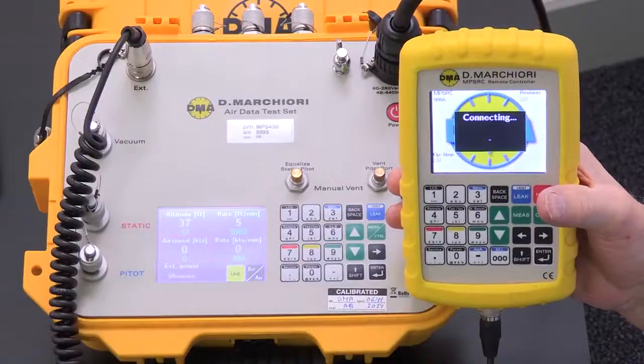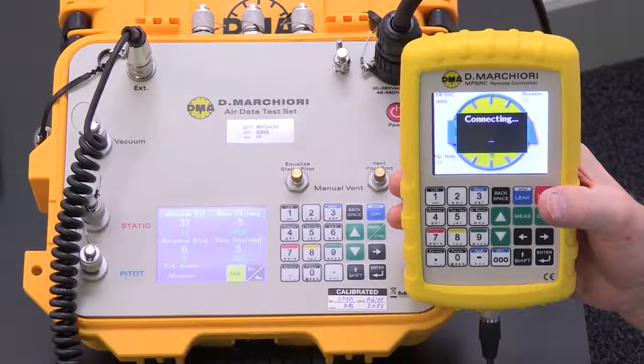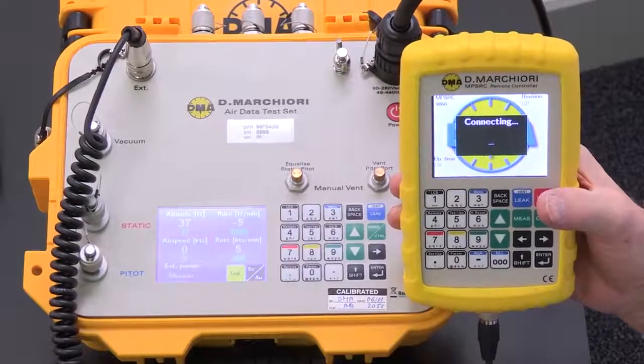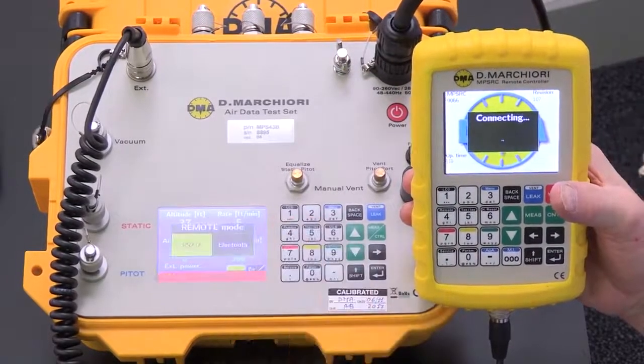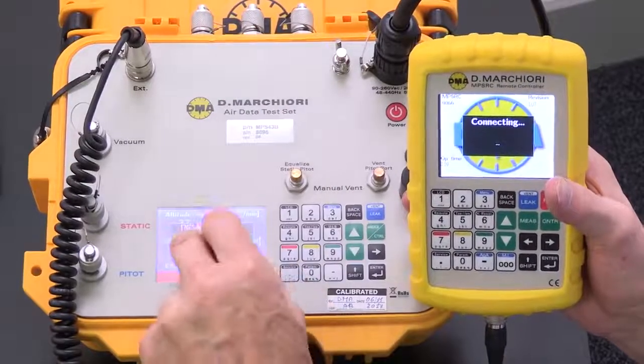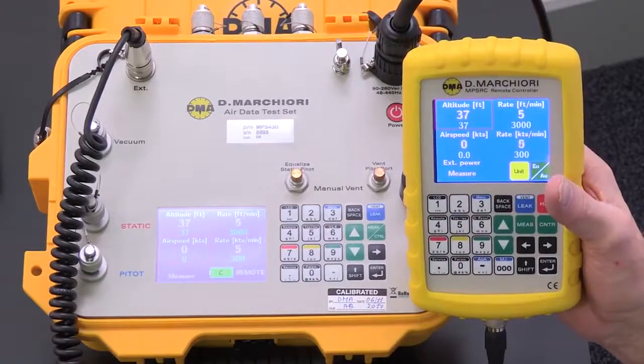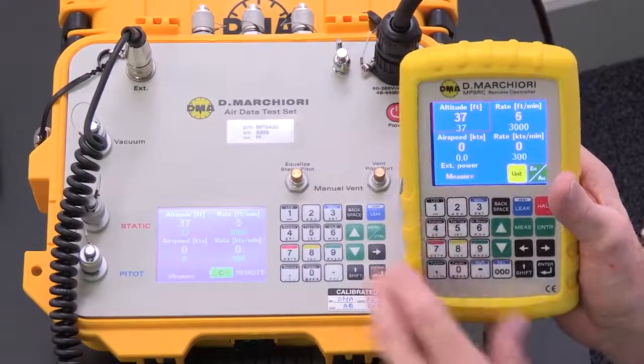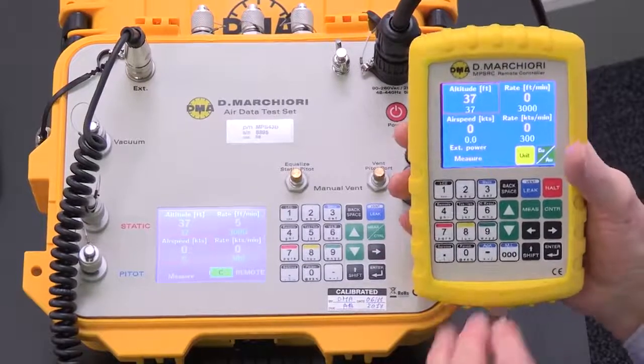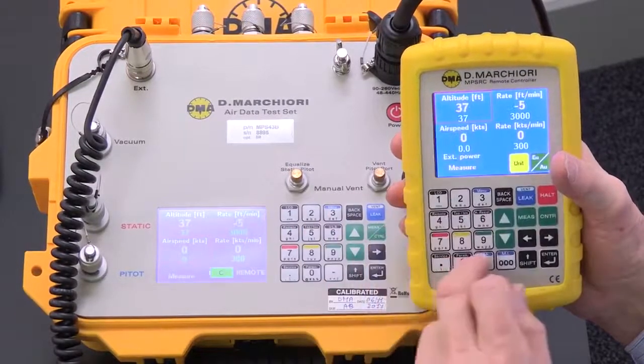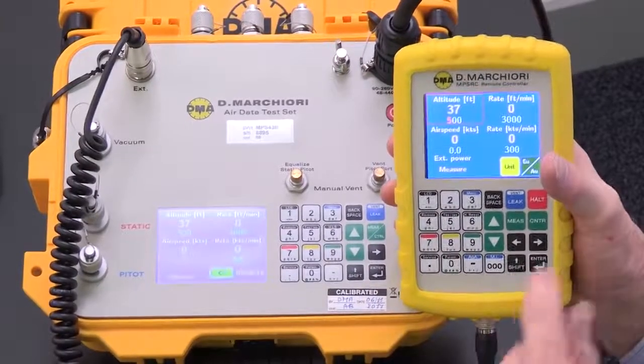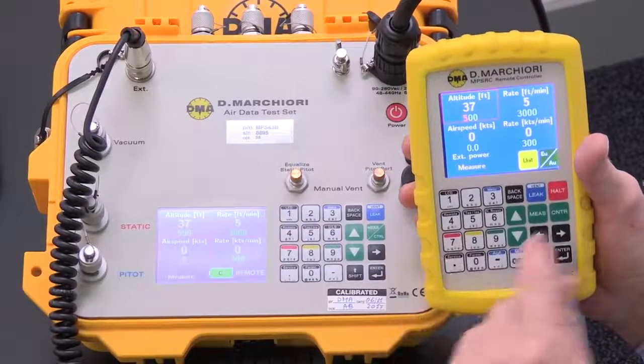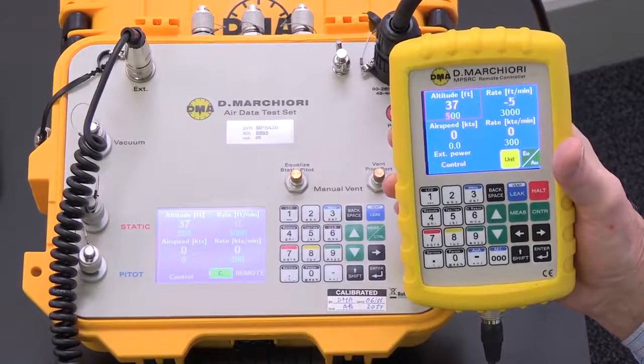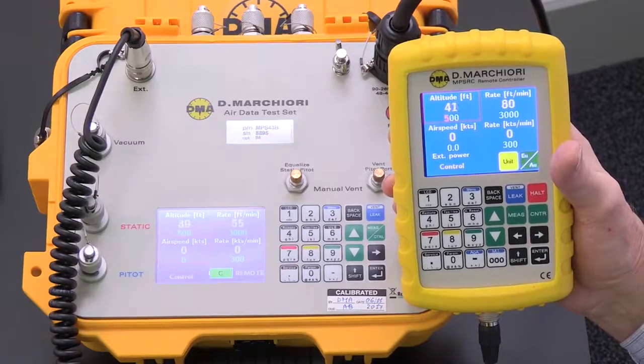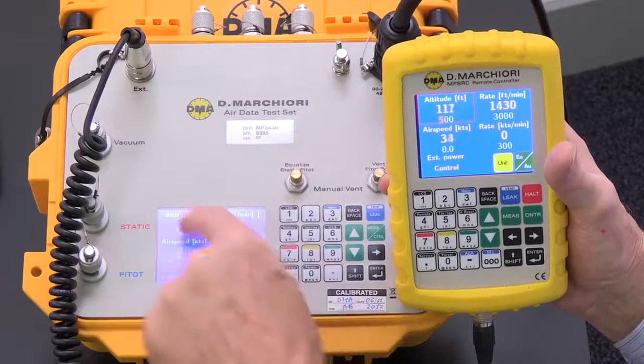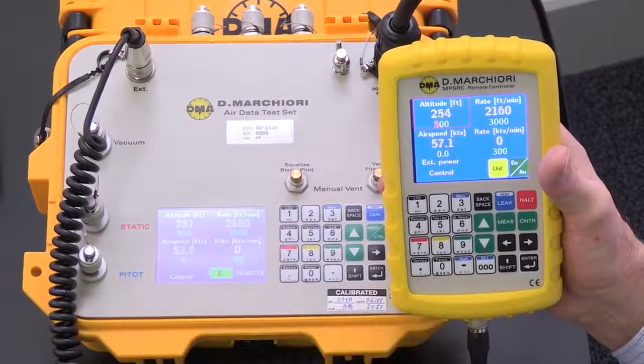Okay, we've connected the MPS-RC, and we're still controlling from the screen. If I want to put control onto the remote here, I go to Shift and Remote. It asks which type of remote we'd like - we're on RS232. We press that, and now we're in control on the remote, as simple as that. The keypad is almost identical, with a few little differences, but nothing important. Now if I go to altitude and say go to 500 feet, enter, I'm in control, and we'll do that when I go to control. And here we are - we're now operating it from this remote, and it takes us to the value we're interested in. A plus point is that it also shows you on the local unit, even though you're not controlling it from there any longer.